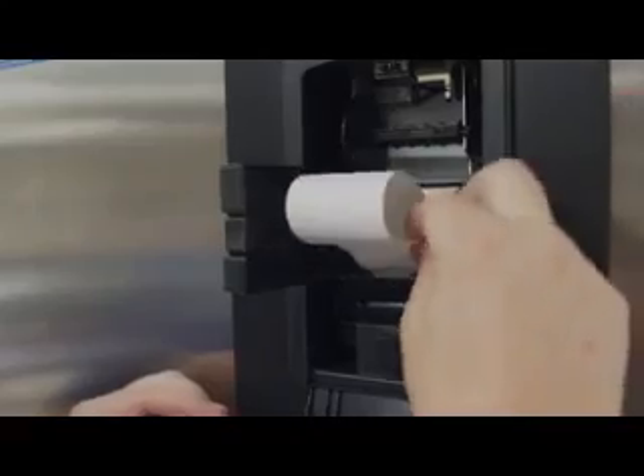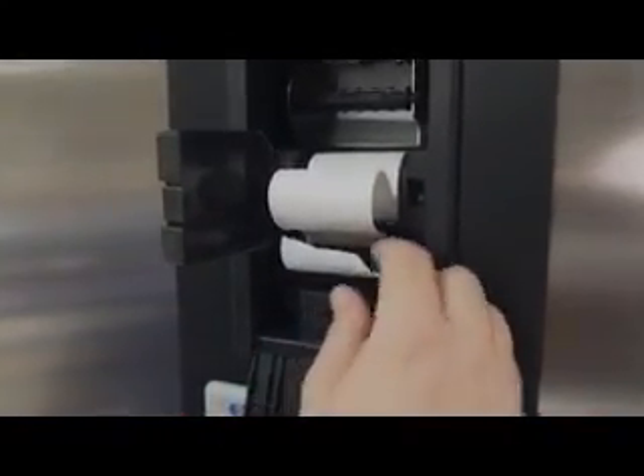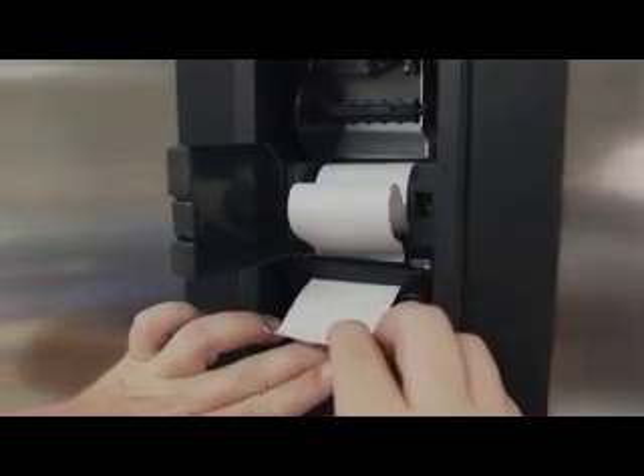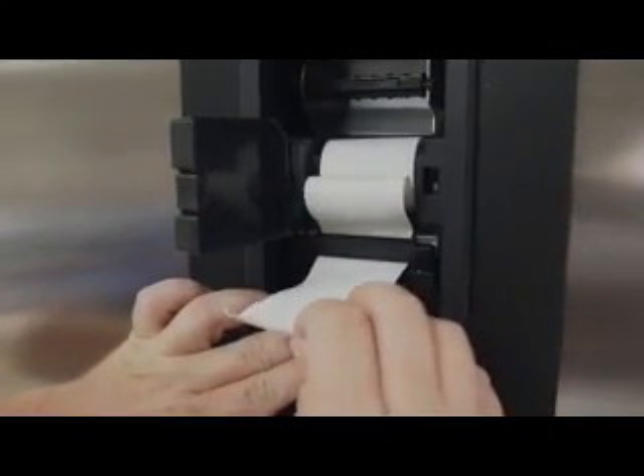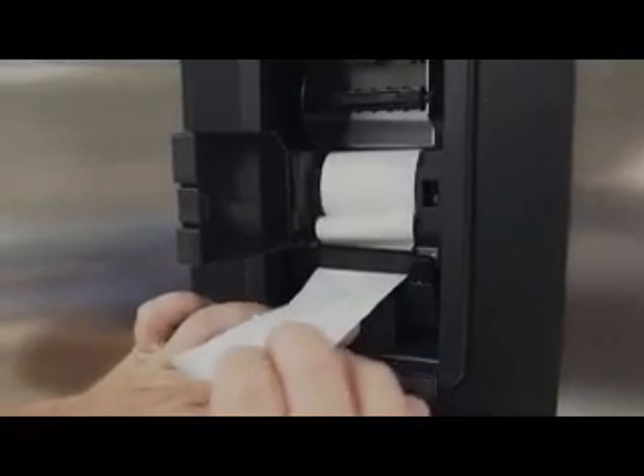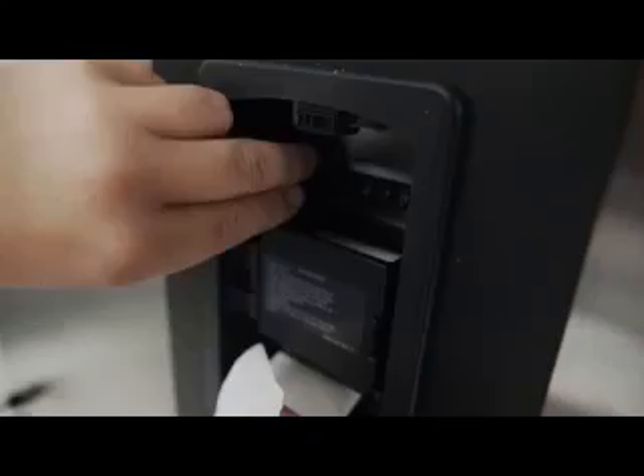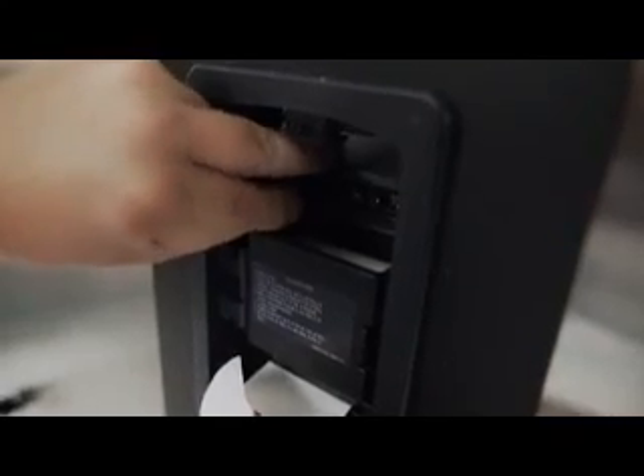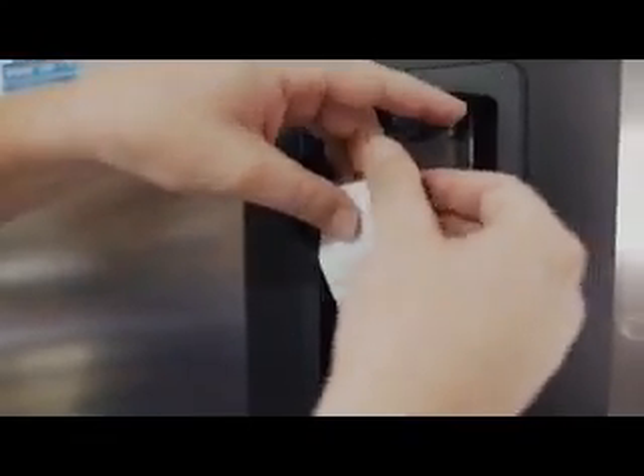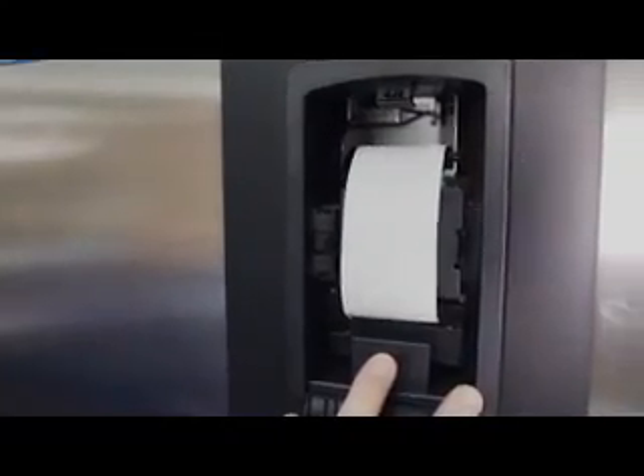Insert the end of the paper into the printer roller mechanism, just behind the ink cartridge. Press the paper feed button on the printer until the paper advances through the printer mechanism and ink cartridge and out the bottom. Continue pressing the paper feed button until about 18 inches of paper hangs out of the printer. Remove the take-up spool from the drive by inserting your fingers in the cavity and lifting slightly to pull the spool out. Insert the end of the paper into the slot of the take-up spool. Coil the paper around the take-up spool until it's secured. Reinstall the take-up spool in the bracket and manually roll up the slack paper. Close the printer door.